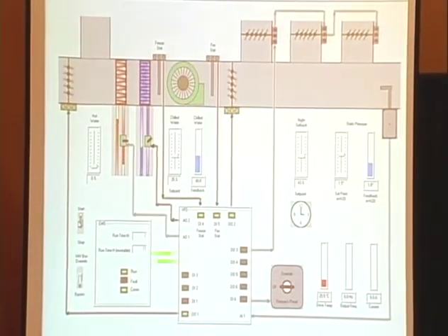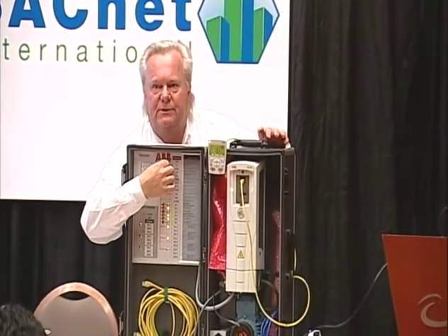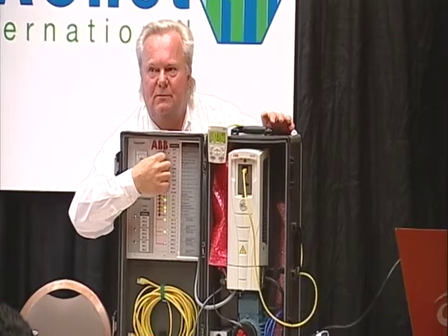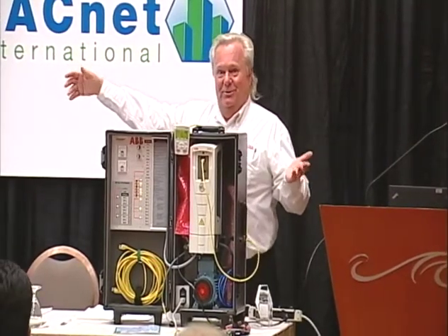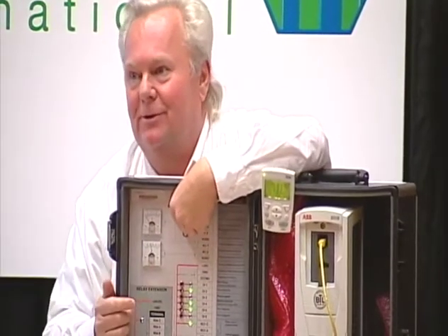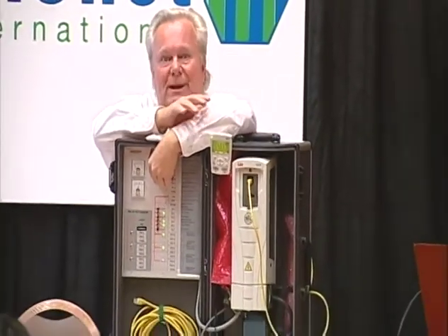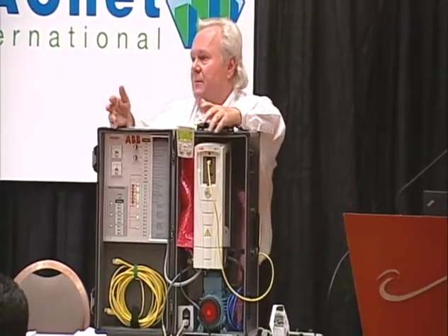So once again, I'll start it. And when the damper end switch is closed, I'll take off and run. So I'm controlling static pressure based on this feedback. I'm controlling the chill water loop based on this feedback. Once again, now if I lose communications, those are standalone automation loops going on here. So the graphic won't change because I'm not connected to my computer. But those of you in front will see my analog output to the valve is still varying, and all of you can hear I'm still controlling speed. So once again, distributed digital control, controlling the application from here instead of from the building automation.